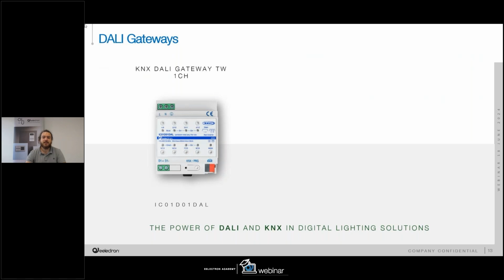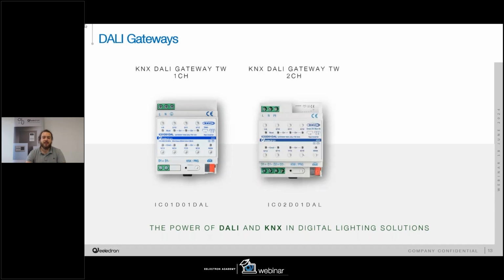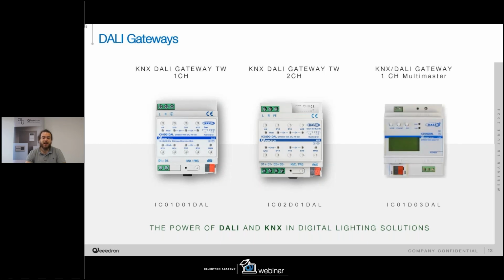Starting from the gateways, we can start from the IC01D01DAL, that is a single master application DALI gateway with one channel. Going ahead, we have the IC02D01DAL, that is the big brother. It's just a twin channel DALI gateway, so same features as the first one, but with two DALI buses in the same device. And we finish with the multi-master application with only one channel DALI bus.